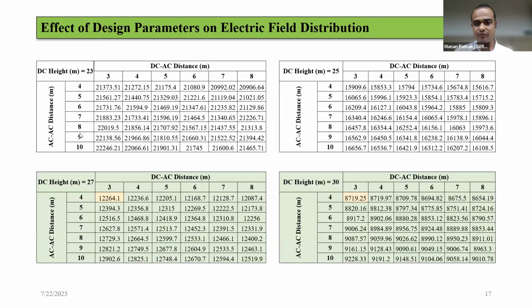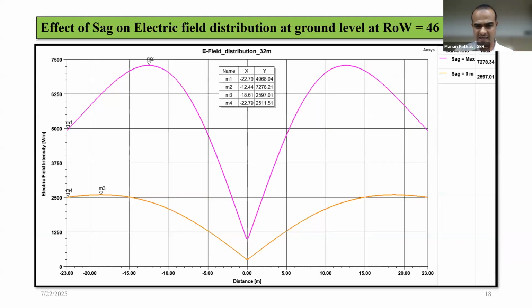If you verify the fourth table, with a DC height of 30 meters, and we change the AC to AC distance from 4 to 10 and the DC to AC distance from 3 to 8, we have certain numbers which keep the electromagnetic field values within range. By incorporating those values, we can modify with the help of trial and error, and subsequently put in some sort of algorithm with the help of artificial intelligence. We can prepare a neural network system and justify the conductor positions as per the ICNIRP guideline. So that range we have incorporated.